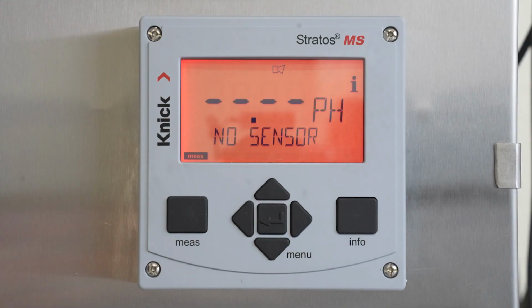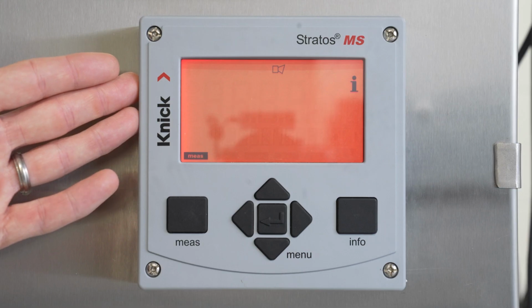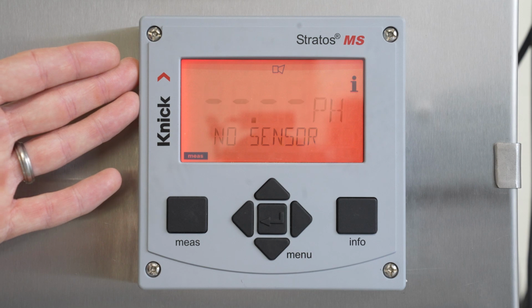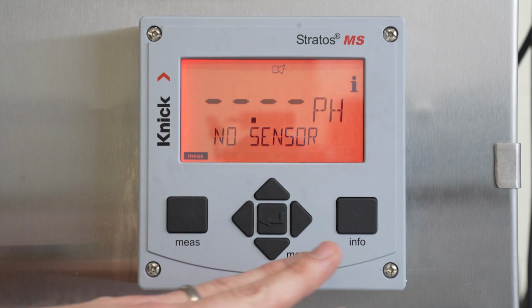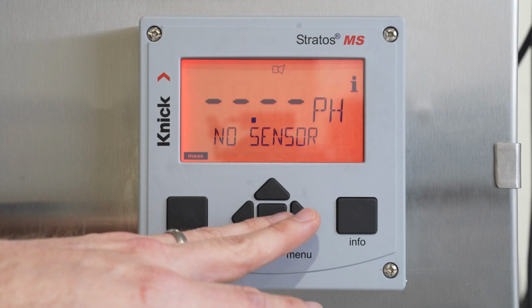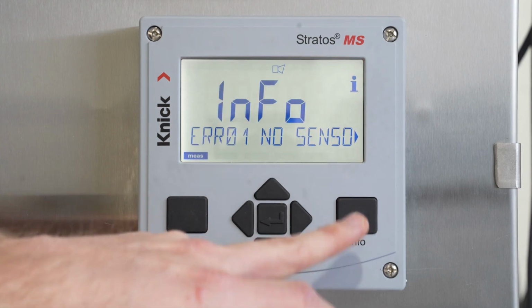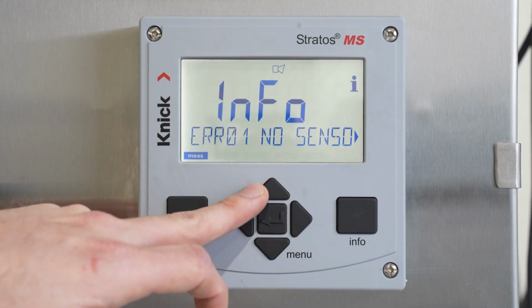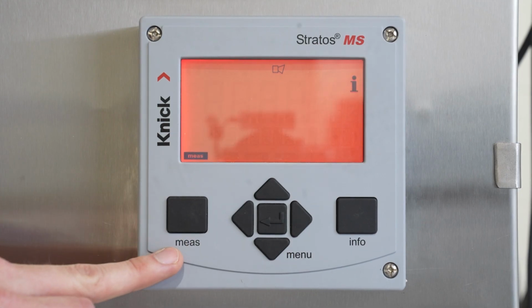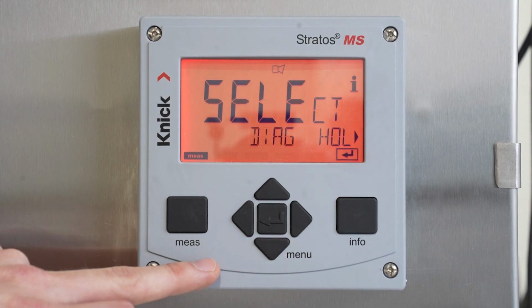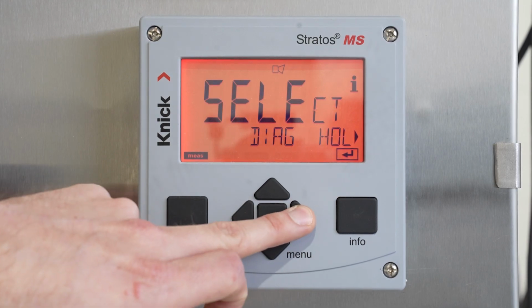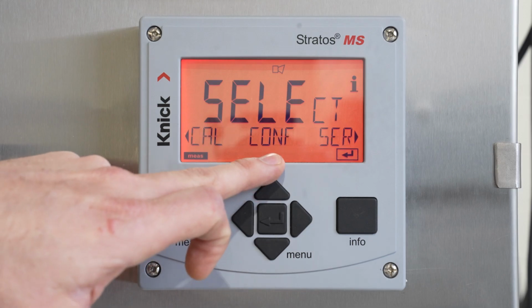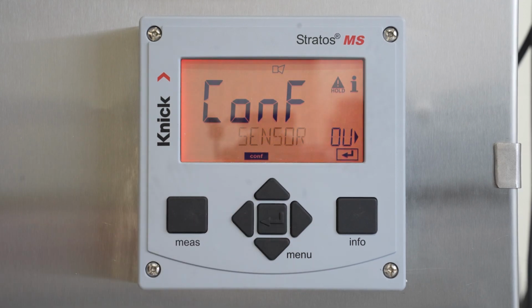The Stratos MS has a multicolor backlit display, which includes a red screen when the transmitter is in an error state, as well as a white screen when the transmitter is in measurement mode without any errors. Our buttons on the faceplate allow us to toggle through the menu navigation, view more information or error codes, as well as go back to the main measurement screen. We will begin our setup and configuration by pressing the menu down arrow. Next, we will scroll to configuration and press enter.